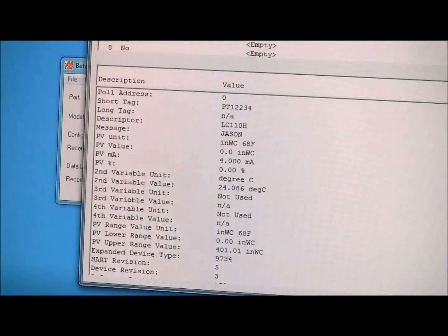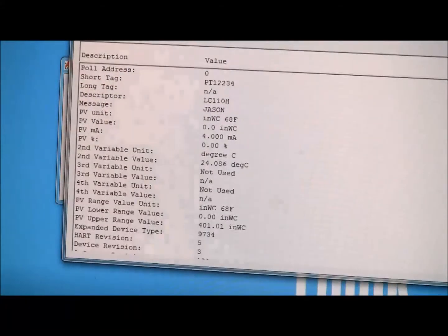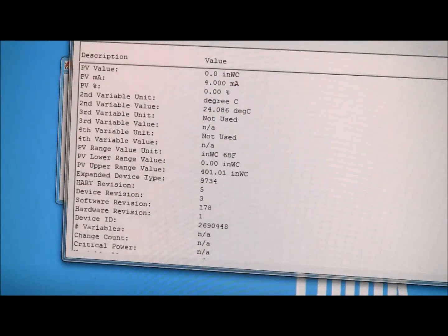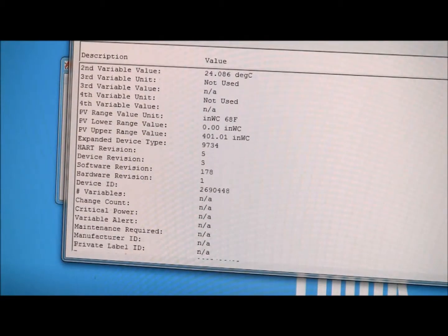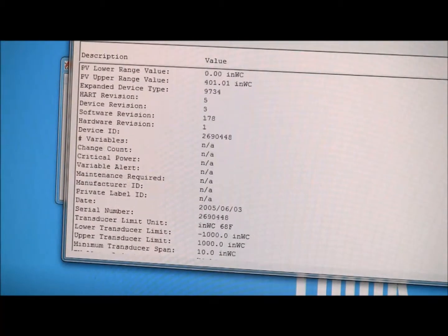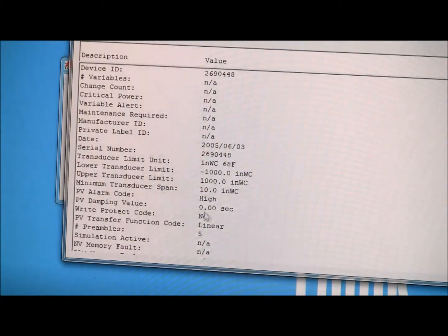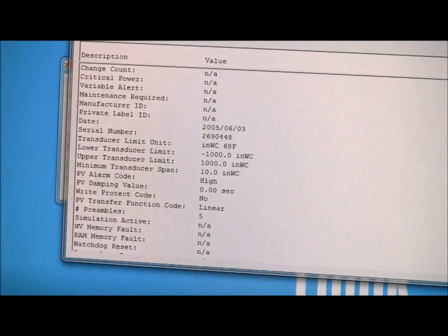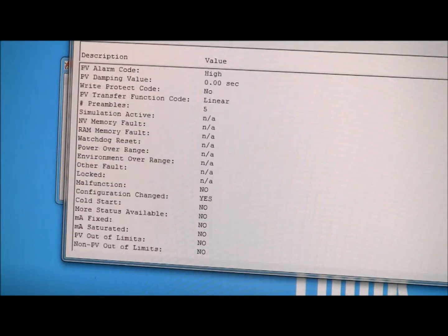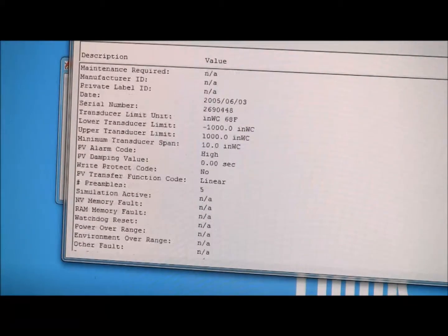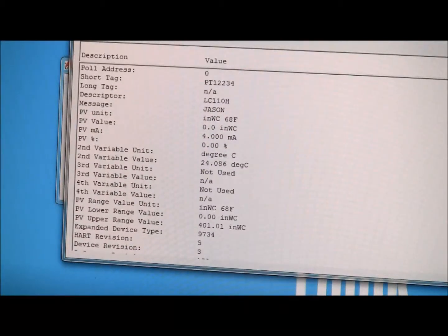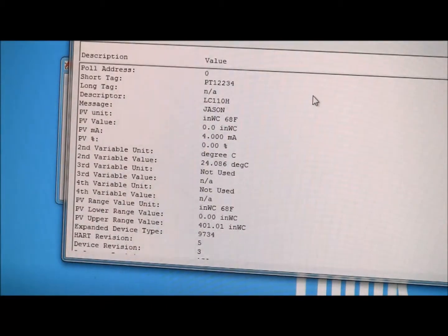So what I've done is I've just set the time, and you can see right here on the screen, everything about the transmitter. So we grab that config, it's telling me the upper range, the limits, alarm set, date, serial number. So I have all that right on my screen, and I can save that as a CSV or PDF. So I've just documented that transmitter.